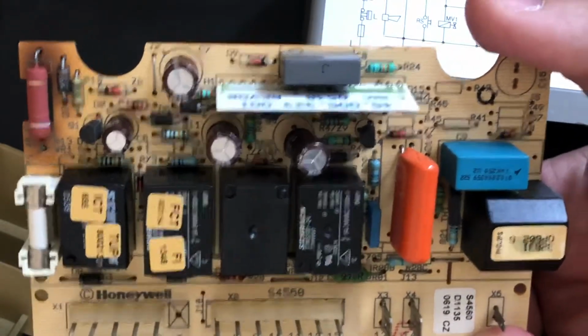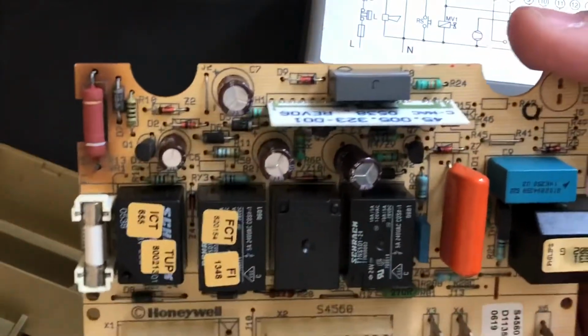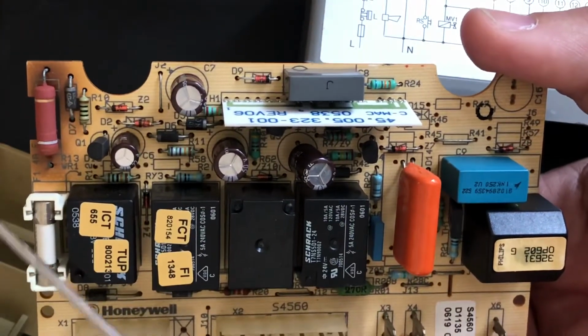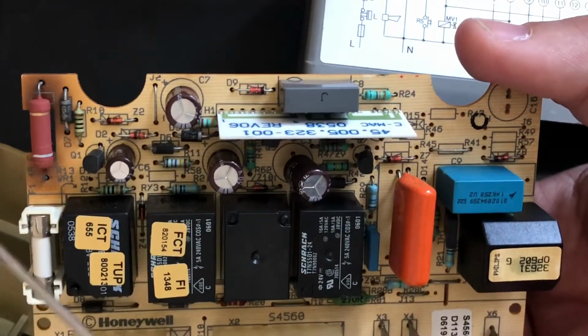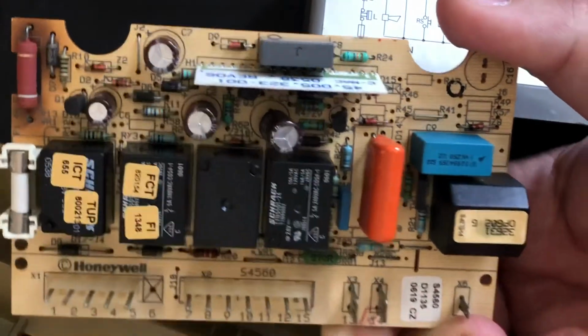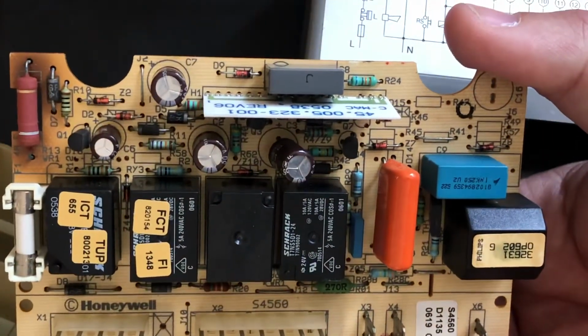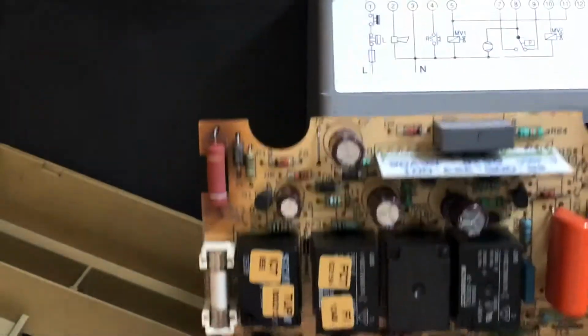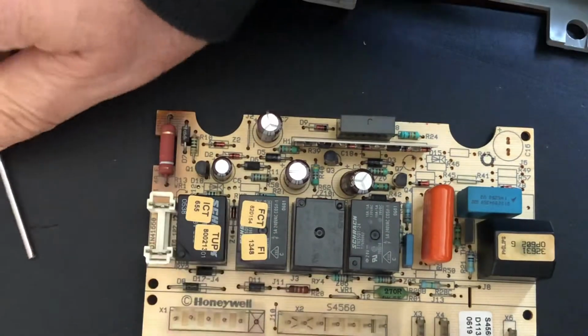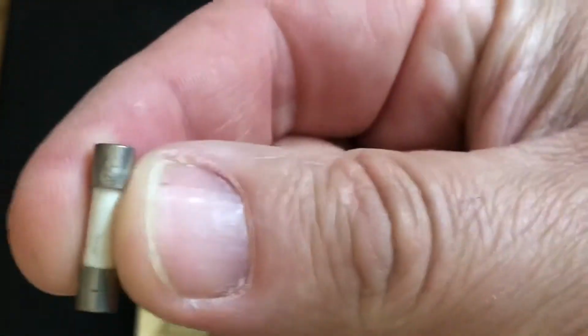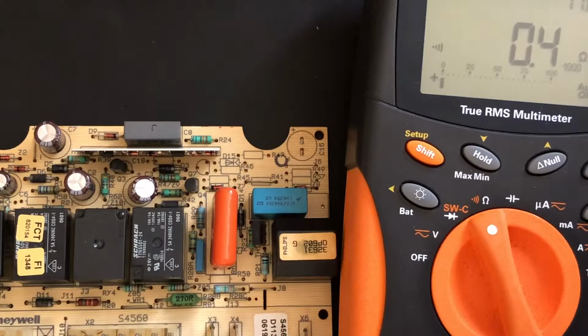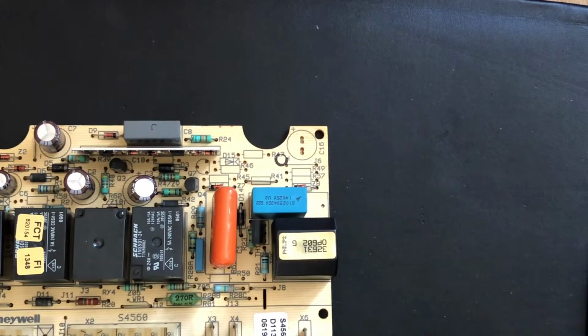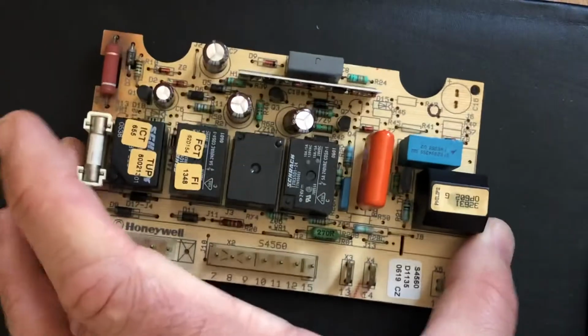But what can you do? Before you do anything, and I think it's right for you to do that, you can look into this fuse. You check this fuse, you pull the fuse out and you test the fuse. If the fuse is not okay, you replace it, but it's good to make sure that you use the appropriate fuse. So you take the fuse and then use a multimeter to check it. A good fuse will read 0 ohms. Forget about the other 3.4 whatever. That's the multimeter thing.